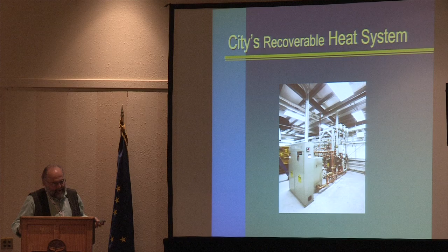So our first phase of the heat recovery system, in 2009, hooked to the new King Cove school, a 40,000-foot school. Since that time, phase 1 has been displacing about 22,000 gallons a year, and over those 4 years, at our current price of about $4 a gallon, that's been over $90,000 annually and more than $350,000 in savings in just those 4 years.